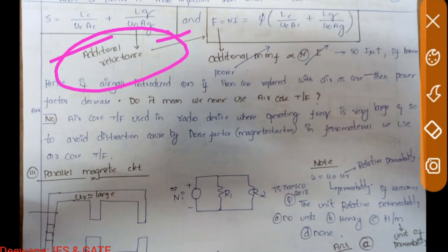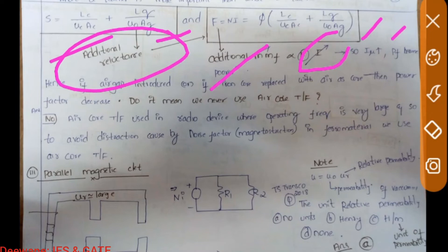If the air gap is large, like in a tube light choke, it gives a humming sound due to magnetostriction at 100 Hz. The additional MMF is proportional to N·I, so current from the source increases. In a transformer, if air gap increases, magnetizing current Iμ increases, and power factor decreases. Final conclusion: if you introduce an air gap, Iμ increases, reactive current increases, and power factor decreases.